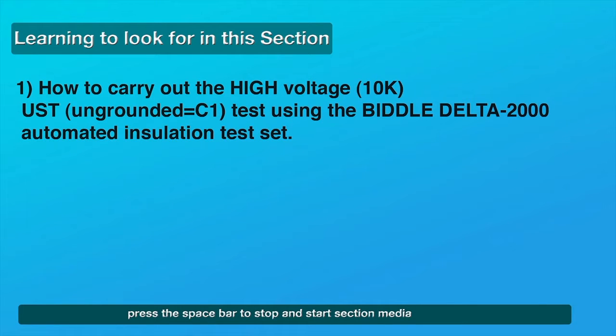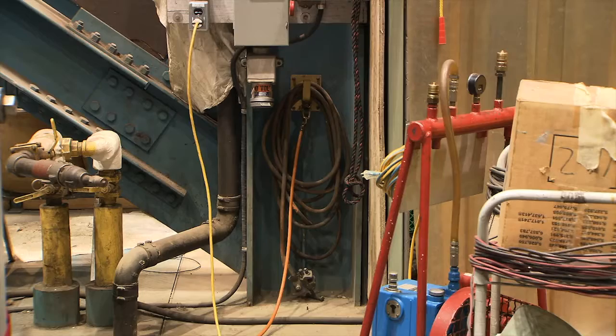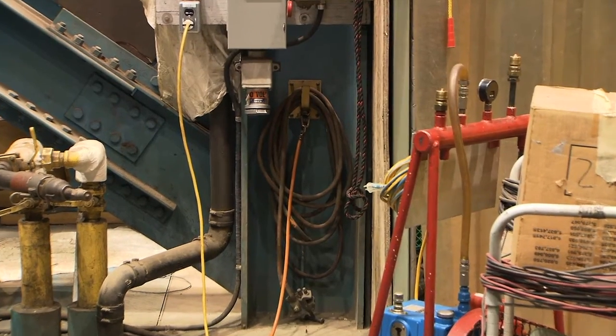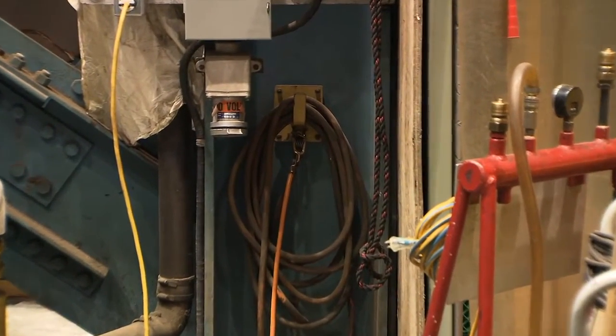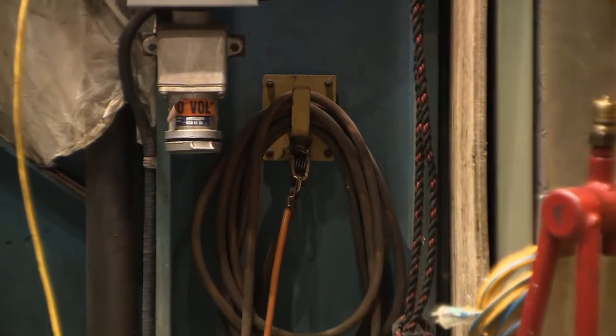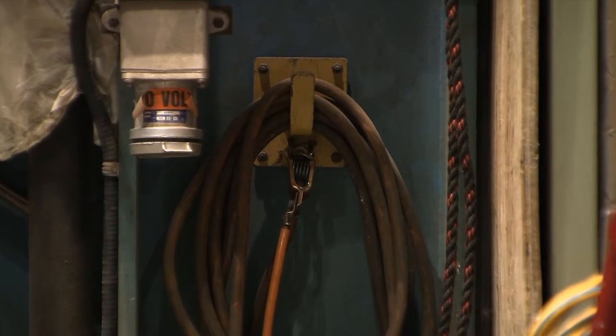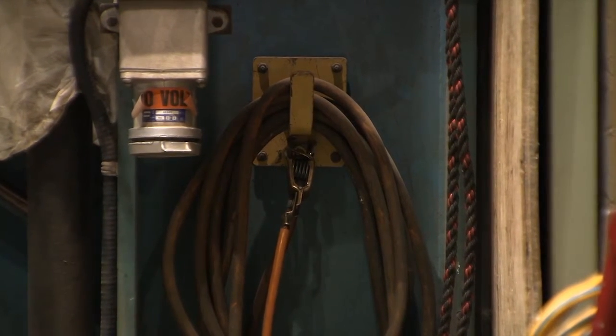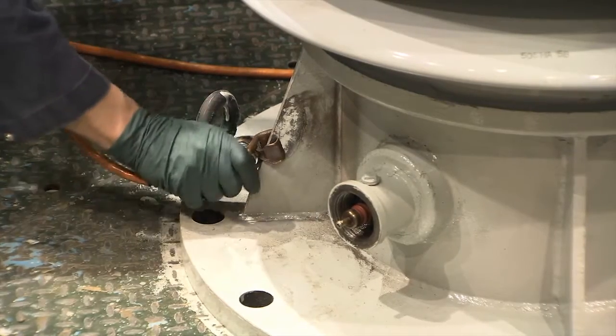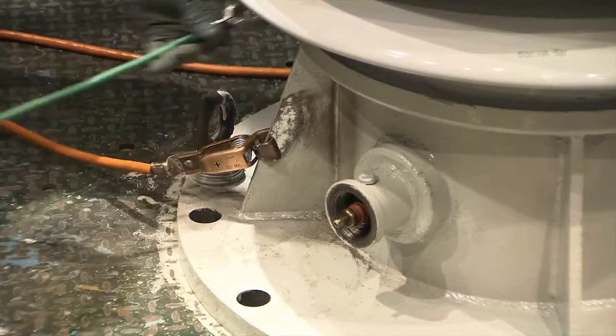The final high voltage UST electrical test, C1, for capacitance and dissipation factor. To make the connections for the C1 test, connect one end of the ground cable to the ground rod for the facility, located on the east side of the bushing shop. Connect the other end of the ground cable to the bare metal on the flange.